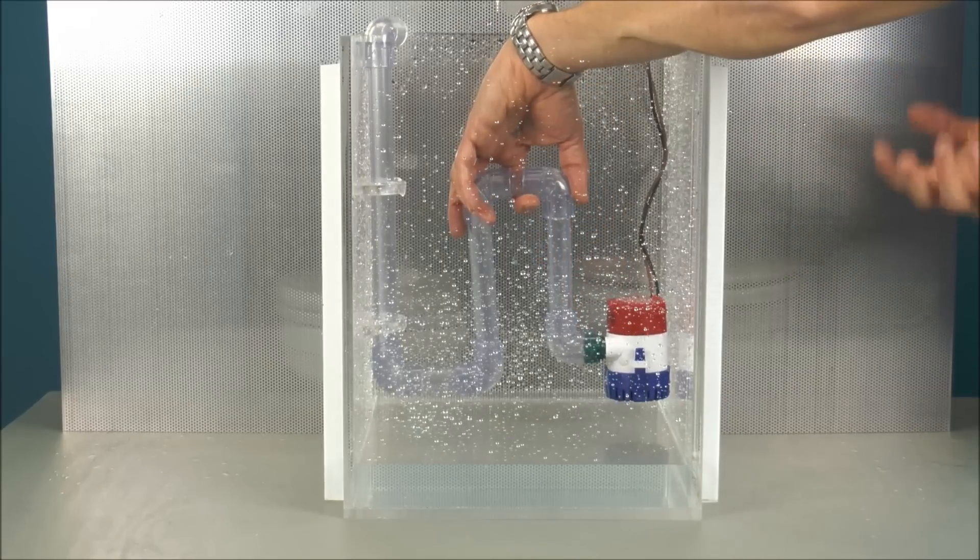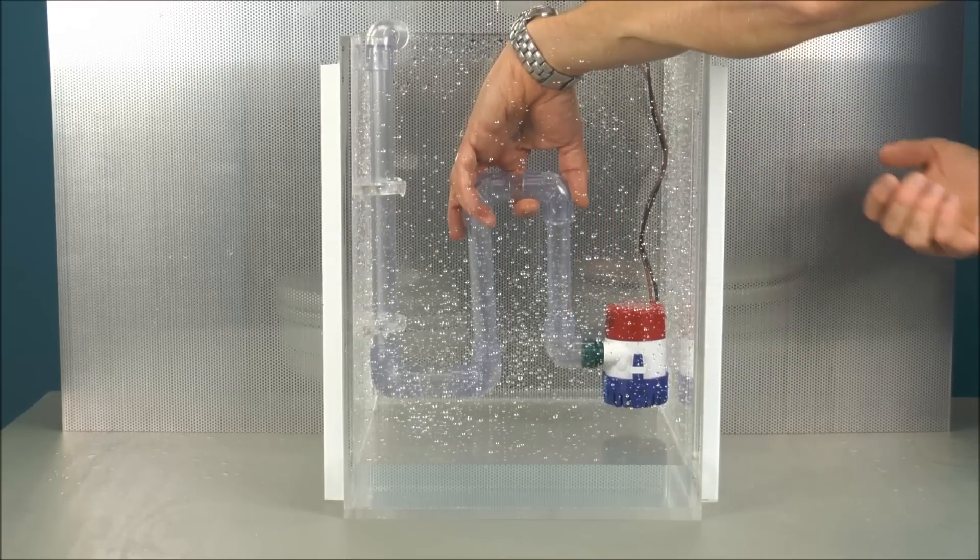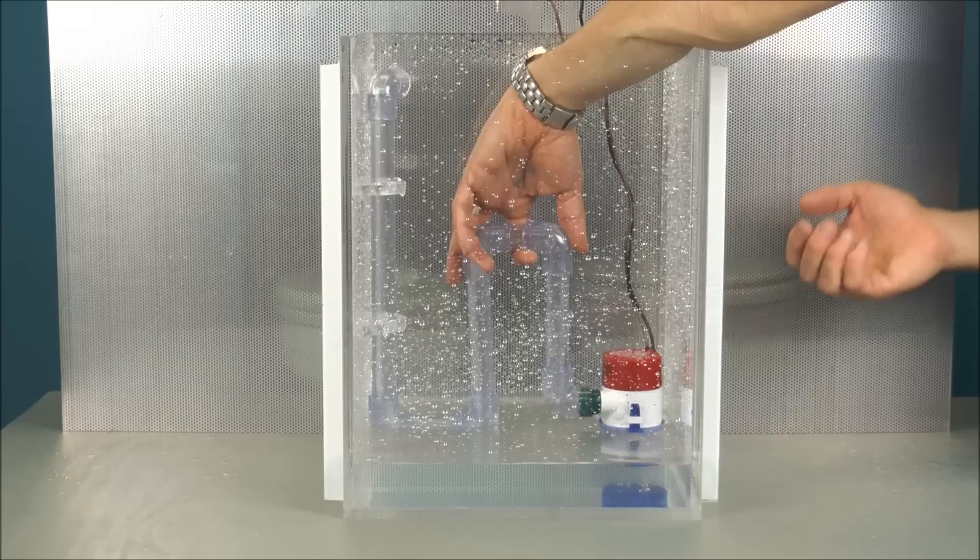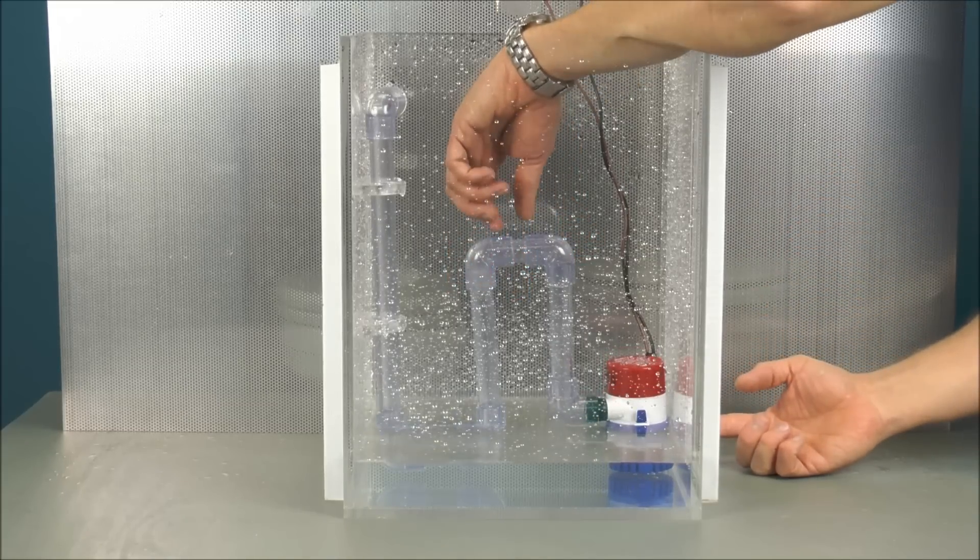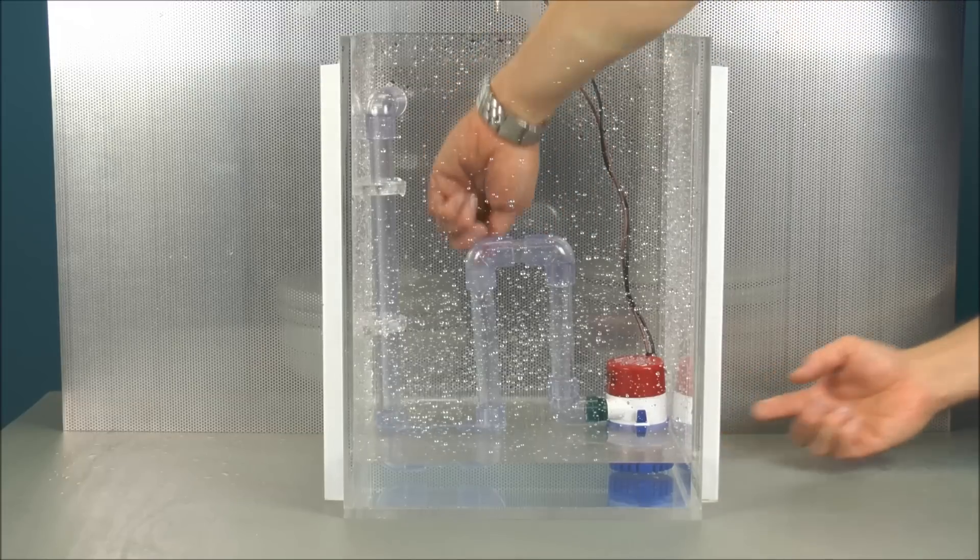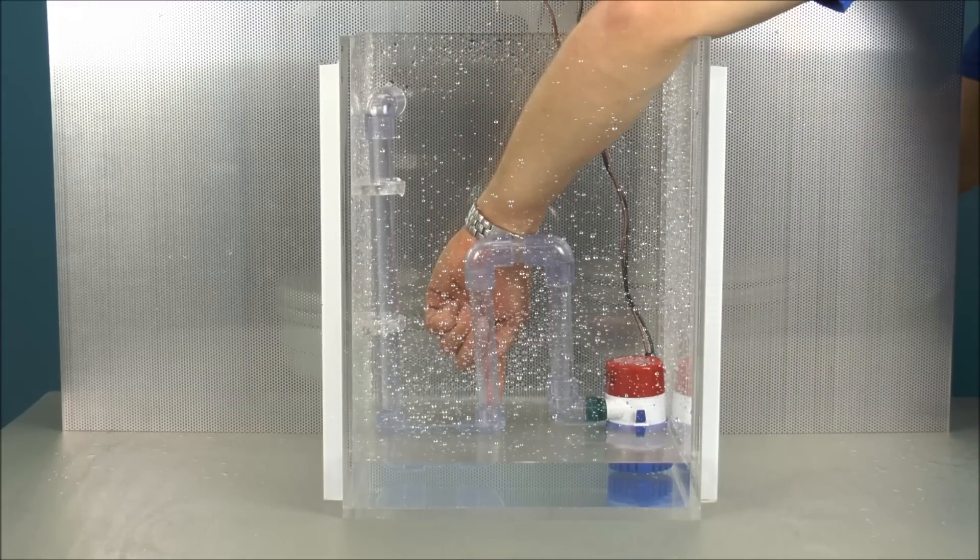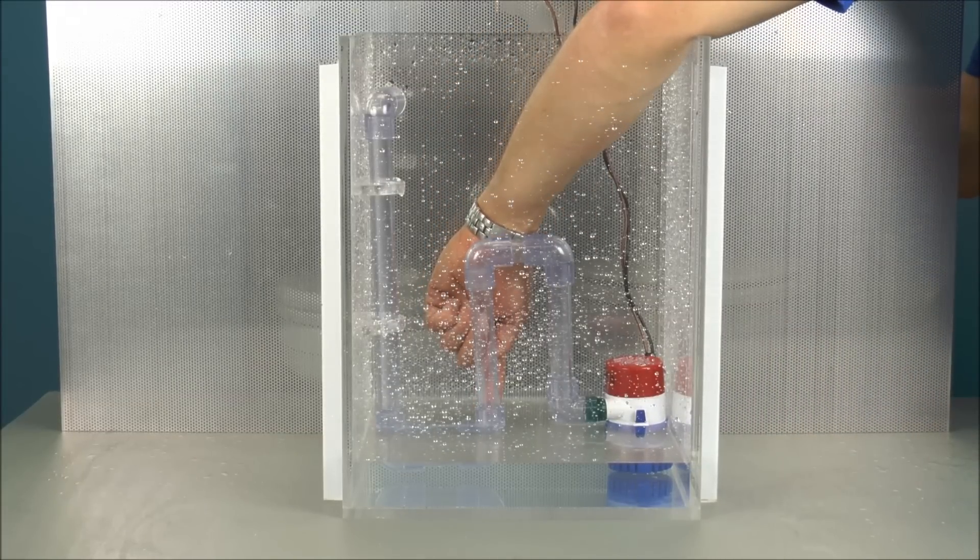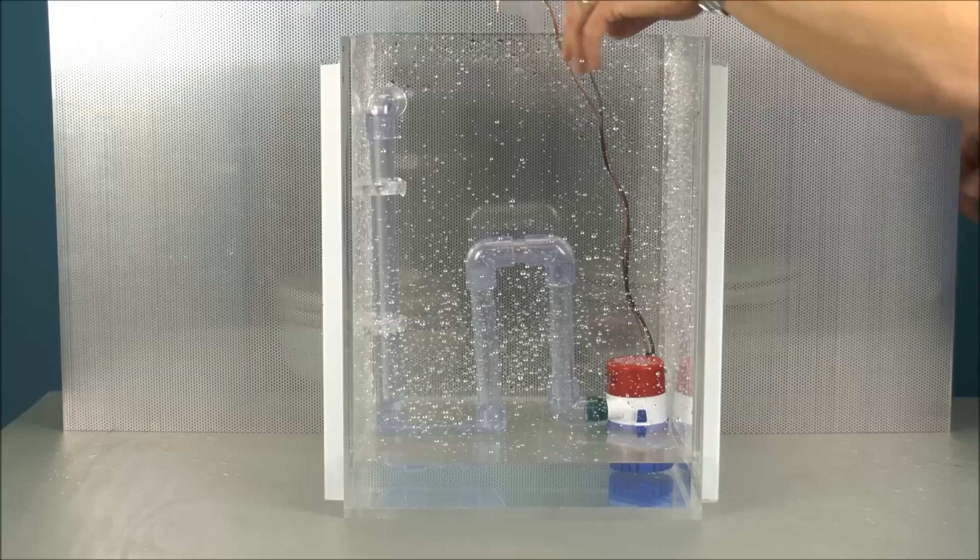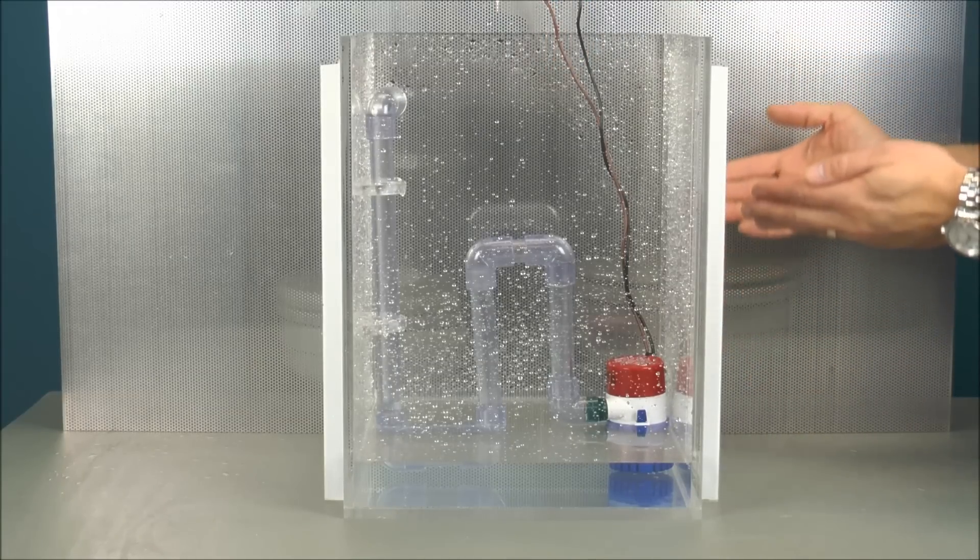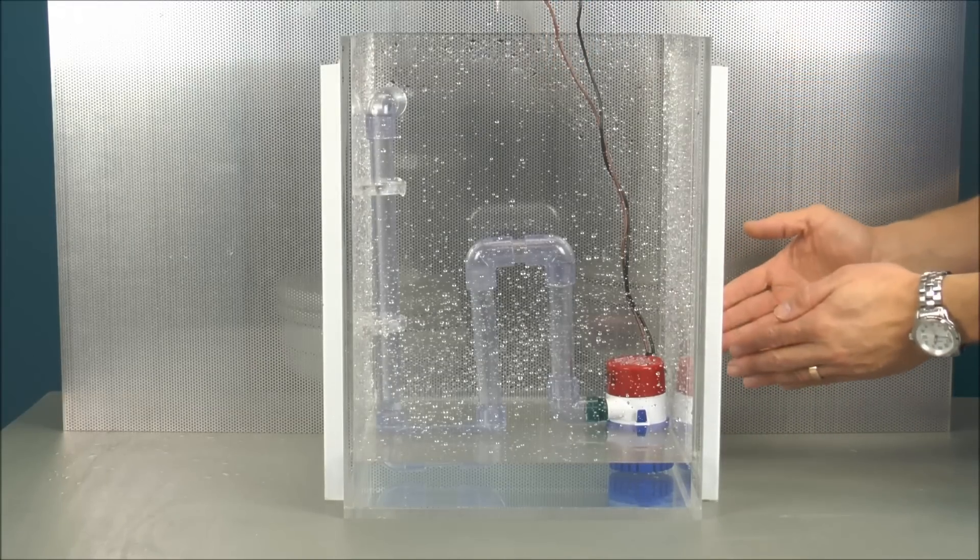Now as the water level rises again, you still have that air bubble that goes from here up and over to just about there where that water level is. Pump switch turns on, it can't pump the water, and that's because these pumps are centrifugal style pumps. They're not self-priming.